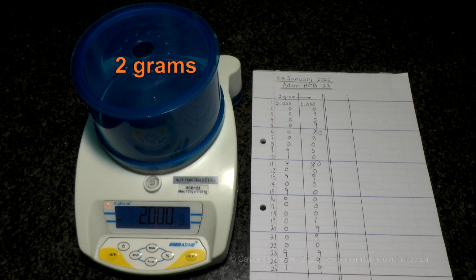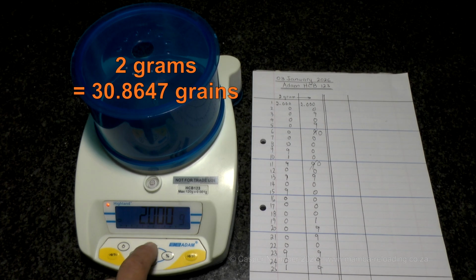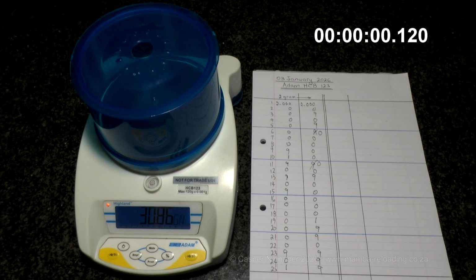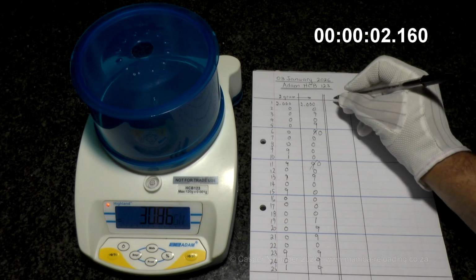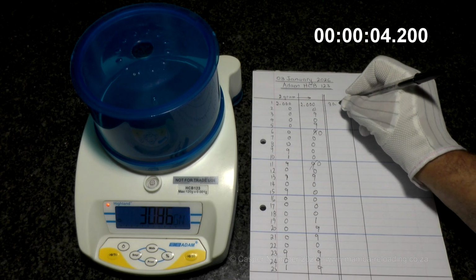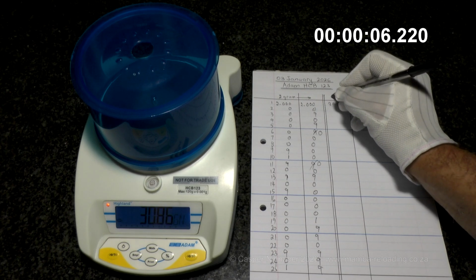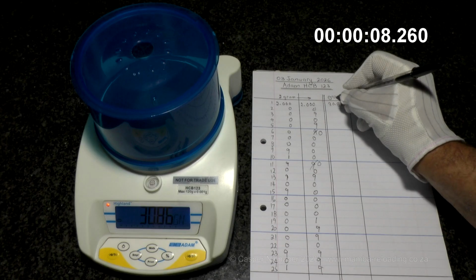2 grams equal 30.8647 grains. When switching to grains using the Mode button, the balance correctly displays the rounded weight of 30.86 grains. I will now weigh the same 2-gram test weight 25 times, recording values to the nearest 0.02 grains.